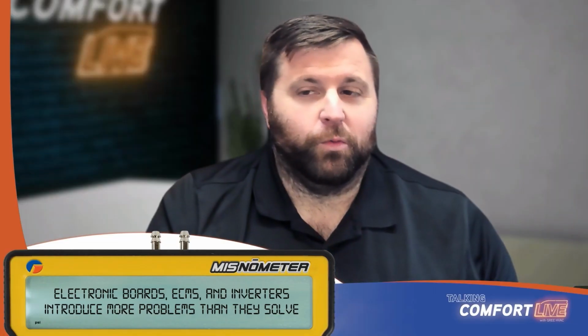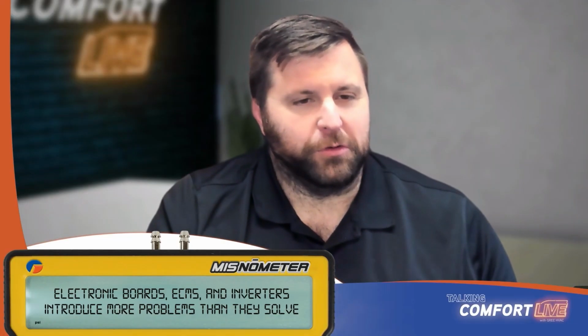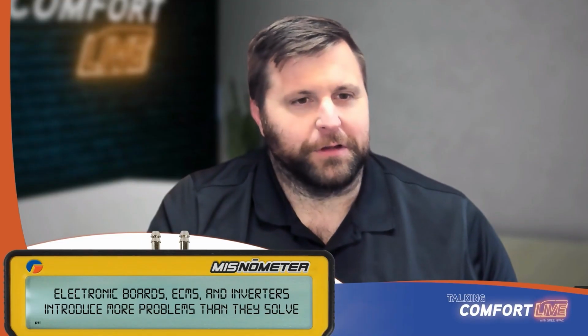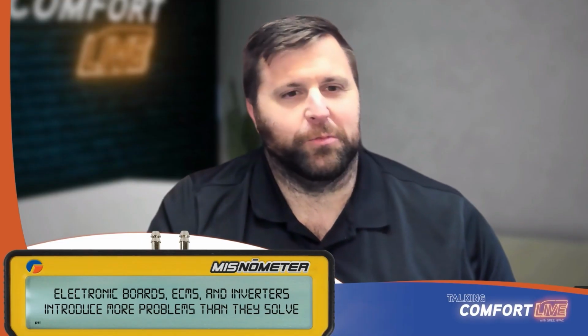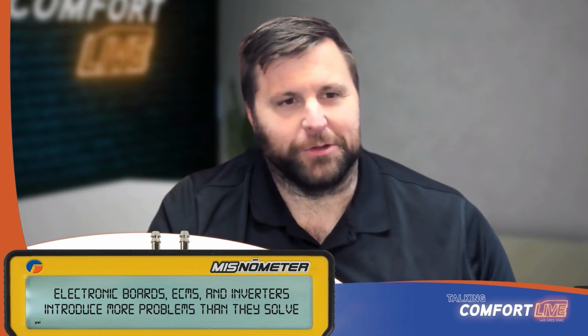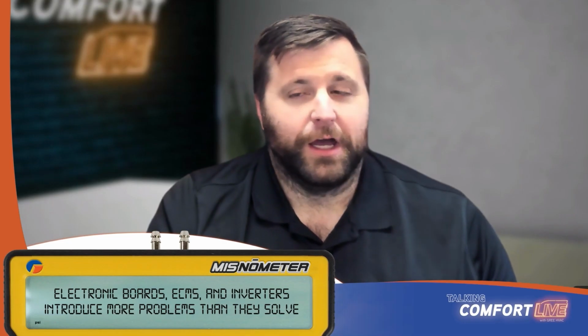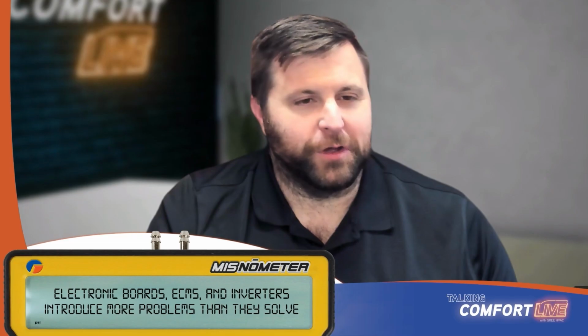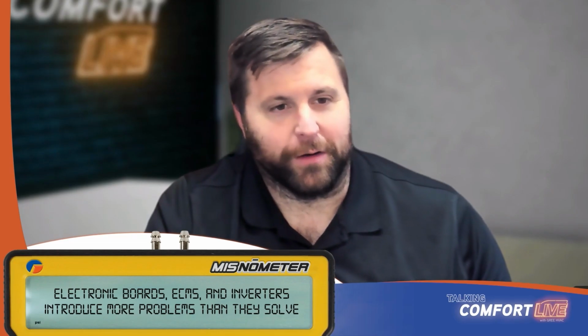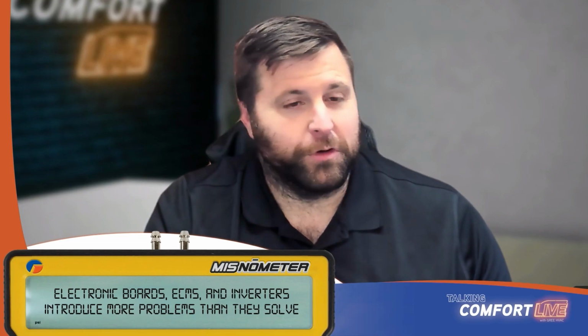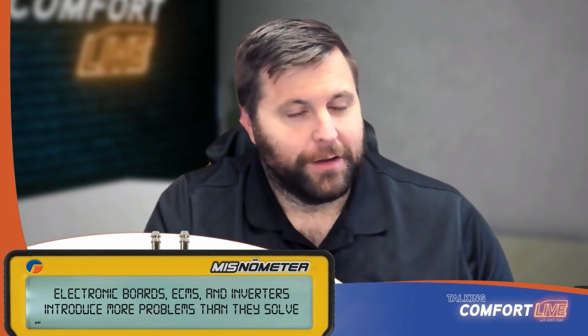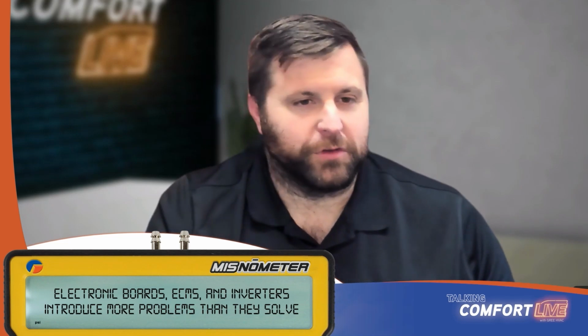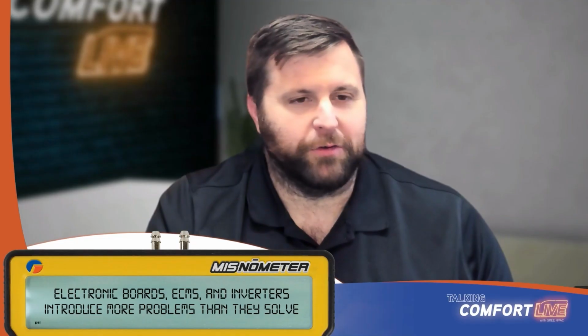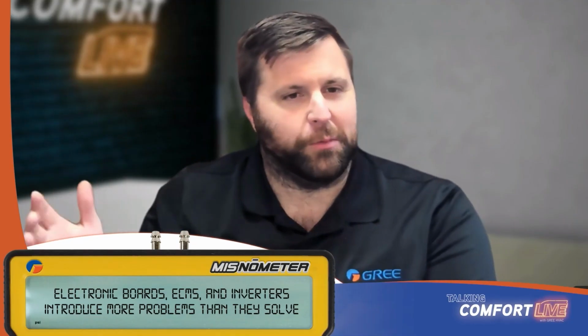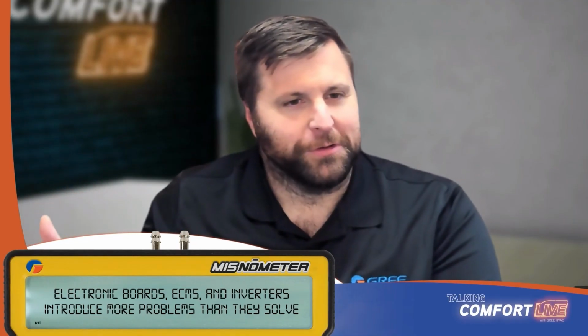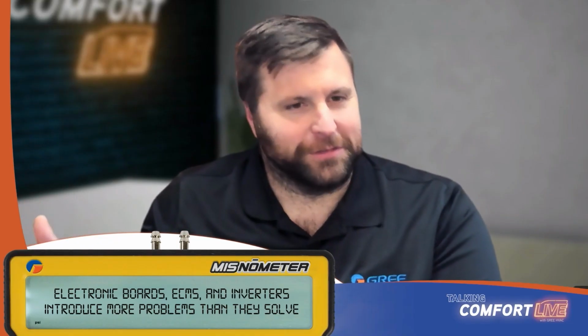And what would have happened with the standard system when you don't set the airflow correctly is that you do end up with a cold coil. You end up with liquid returning back. You do end up with those problems. And those problems may not manifest themselves until you have an expensive repair. Right. 2, 3, 4, 5 years later. And what we found, because of these protections, they're going, hey, we keep having all these problems. Well, it was letting you know that you had a problem within a week of installation, within 2 weeks of installation. That's exactly what it was.